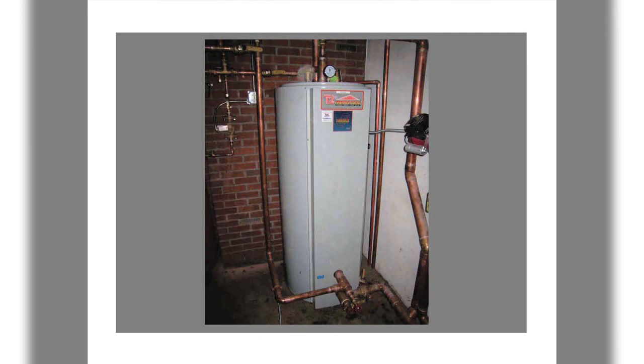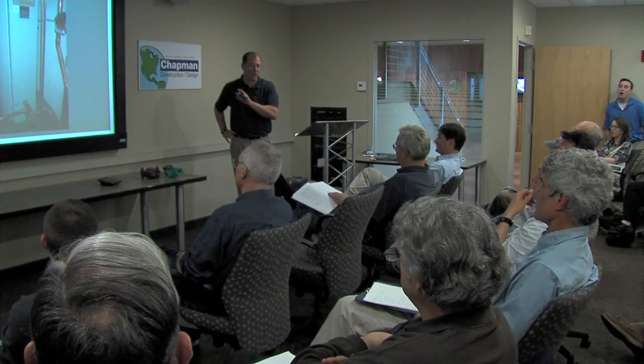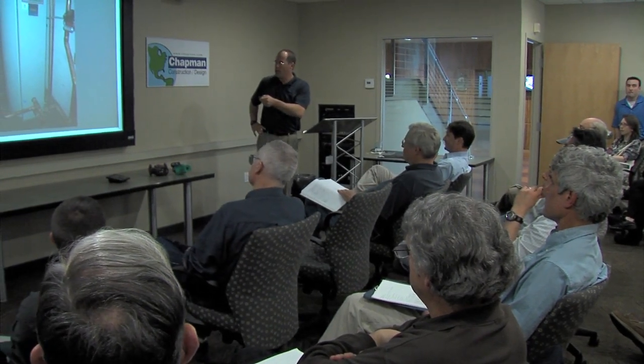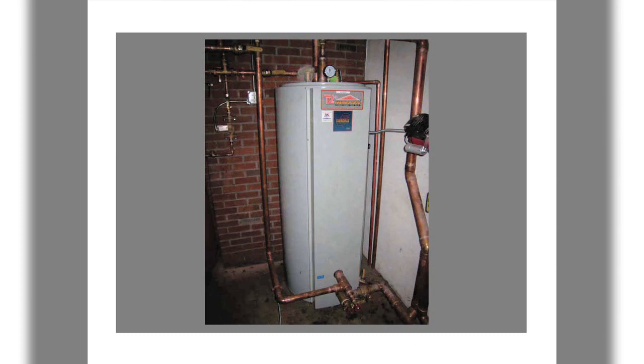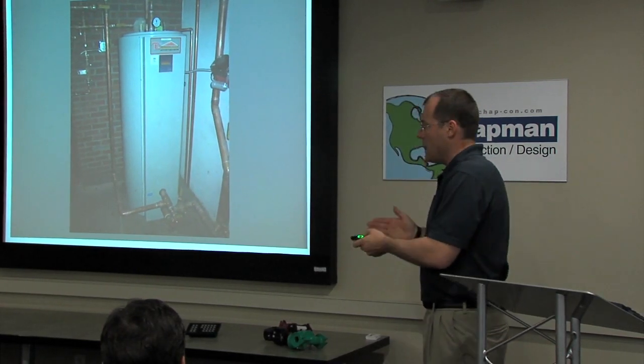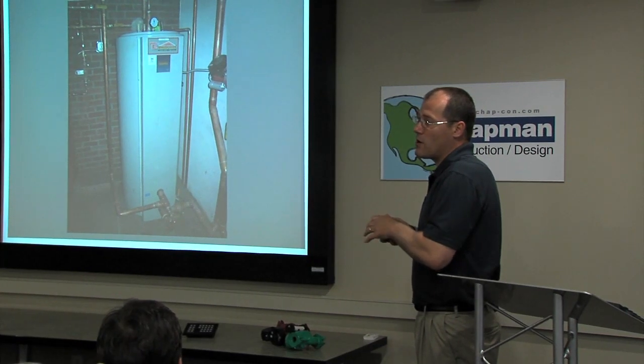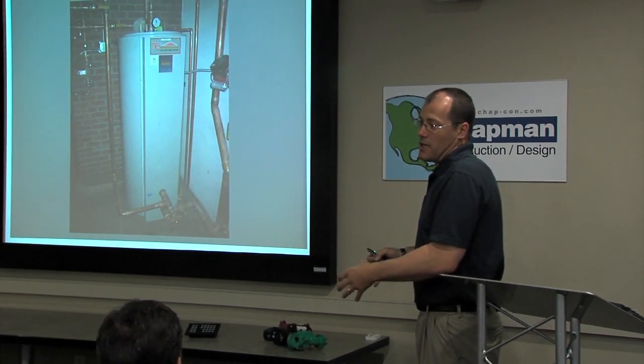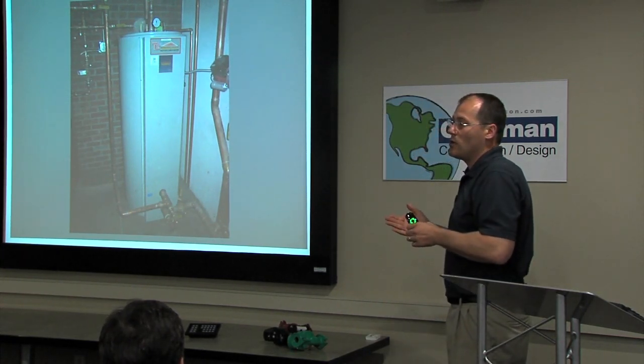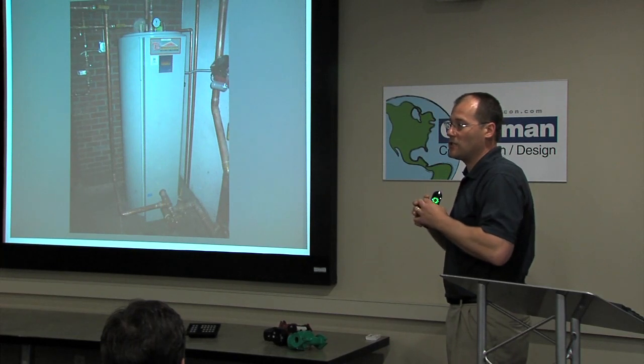I'll ask the question, how many of you are involved in large domestic hot water production? We won't spend a lot of time on it, but just quickly, there's technology now where what you used to see was a large volume of domestic hot water with a coil in it that carried your boiler water around it. Flip that on its ear and have a large volume of boiler water and a small series of coils of domestic water, and your heat exchange surface area gets gigantic.